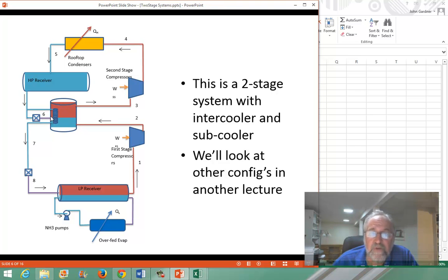And this is actually the refrigeration effect. This valve is controlled by a float on this liquid here to maintain that liquid at a certain level. So it's usually not very much that's going in here, but it's enough to continually cool this. And it has two effects. It brings the refrigerant moving through here to saturation, from superheat to saturation, and it subcools the saturated liquid down here. So the amount of mass flow that's being diverted in here is fairly small, and we'll talk about how much that is in a bit.